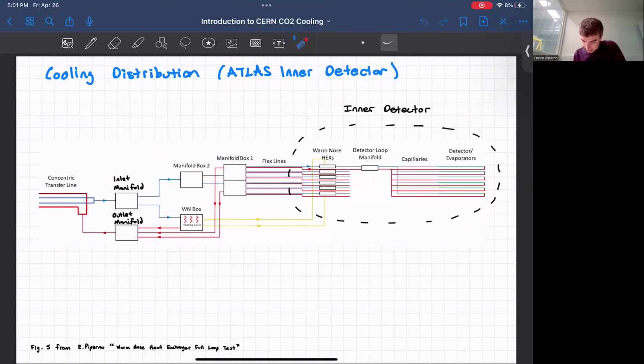The manifold box 1 takes it to the inner detector through the use of the flex lines, which are concentric as we discussed previously. After the flex lines, the flow encounters the warm nose heat exchangers and finally the detector loop manifold. In this manifold, there are 6 evaporators. The warm nose heat exchangers are supplied by the warm nose box, which steals flow from the inlet manifold. These are in series. Finally, all the 2-phase outlet flow goes through the outlet manifold, which then passes into the concentric transfer line. So this concludes the second video, in which we took a deeper dive into 2-phase CO2 and how cooling is distributed in Atlas.